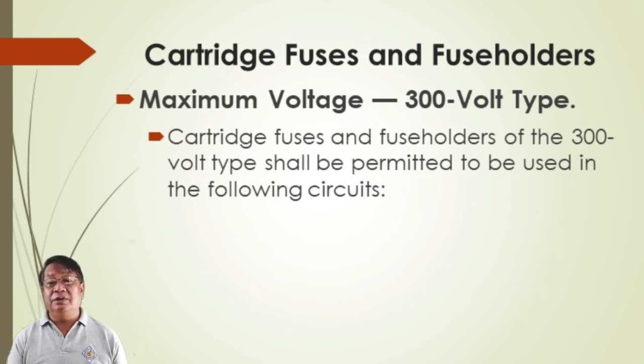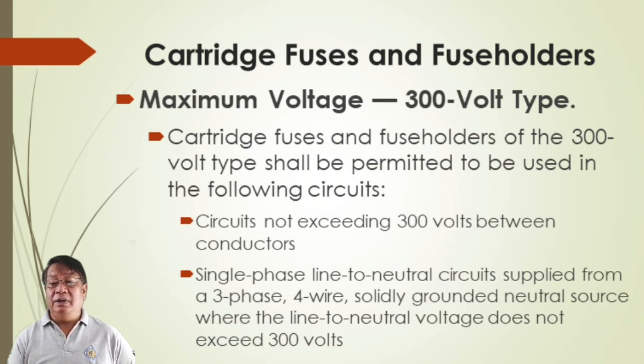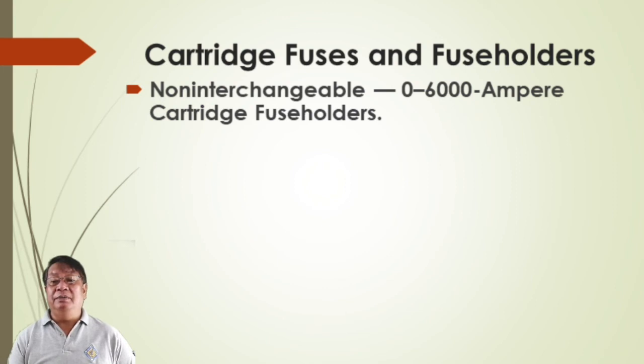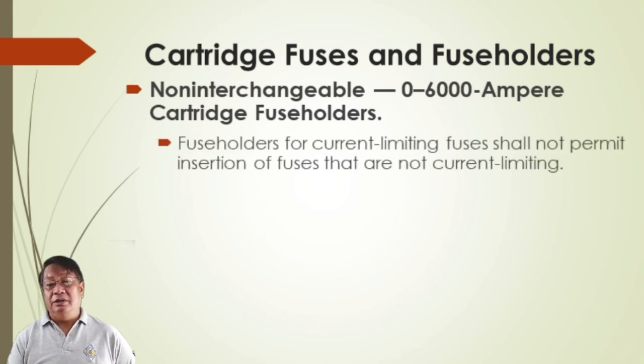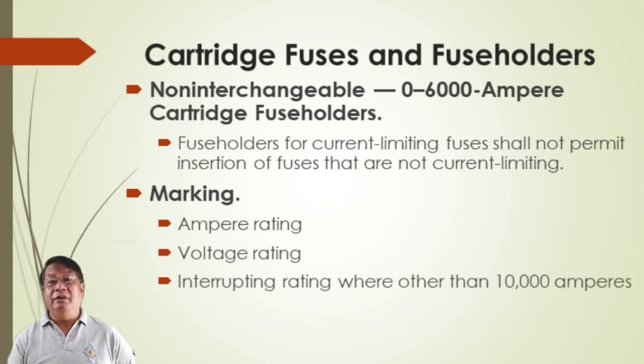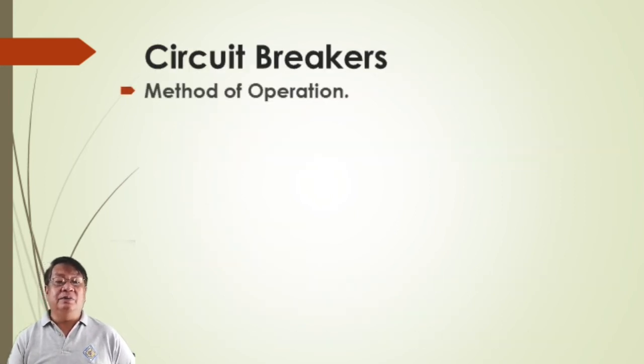For cartridge fuses and fuse holders of the 300-volt type: shall be permitted for circuits not exceeding 300 volts between conductors, and single-phase line-to-neutral circuits supplied from three-phase, four-wire, solidly grounded neutral source. Non-interchangeable 0 to 6,000 ampere cartridge fuse holders for current-limiting fuses shall not permit insertion of fuses that are not current limiting. Markings required: ampere rating, voltage rating, interrupting rating other than 10,000 amperes, whether current-limiting applies, and the name or trademark of the manufacturer.